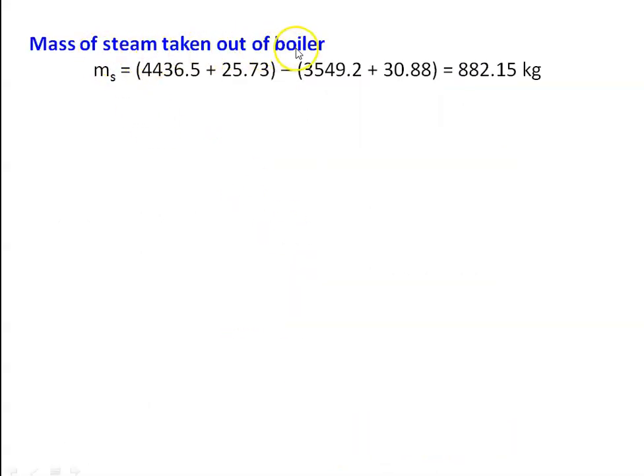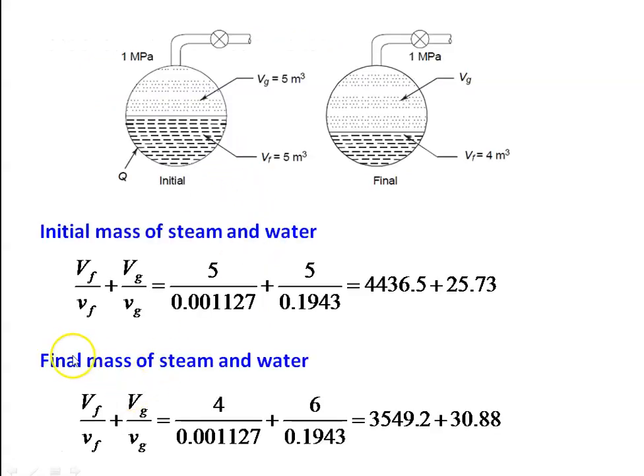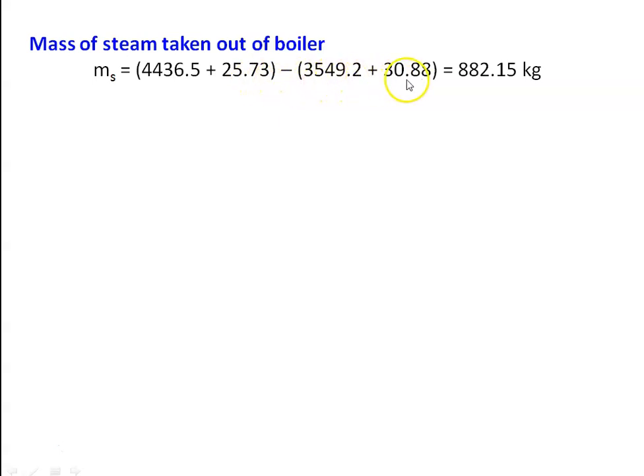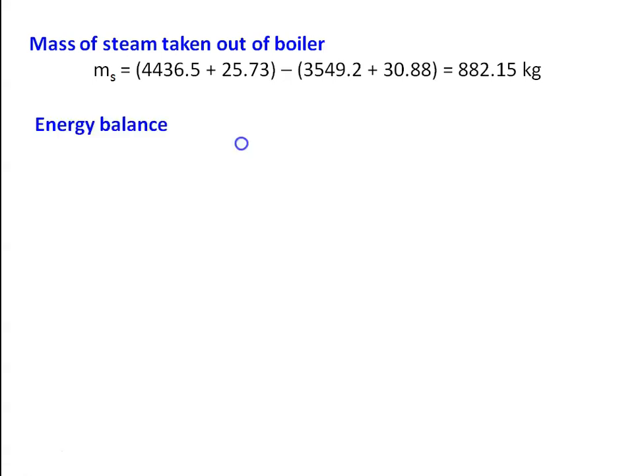Mass of steam taken out from the boiler: Ms equal to initial total mass minus final total mass, which is 4436.5 plus 25.73 minus 3549.2 plus 30.88 equal to 882.15 kilogram. So the mass of steam taken out from the boiler is 882.15 kilogram.